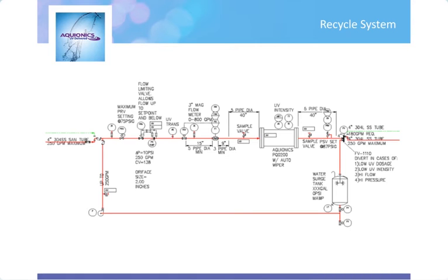So basically the same system. We start with CIP. We go through a pressure reducing valve, then basically on to the next required piece, which is really our flow control valve, into our meter, into our UV lamp, and then out of that into basically our next required piece at least, which is our divert valve. And then our divert valve in this case would send it to a balance tank, if you will. So we would reserve the water and basically recycle it until the system is needed. A system generally can run at about 30% of its stated capacity in forward flow.